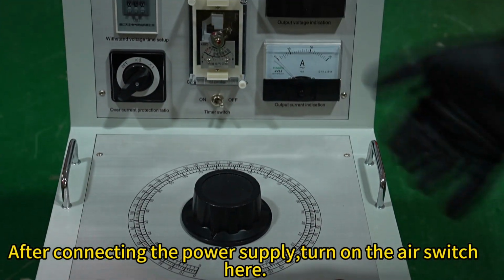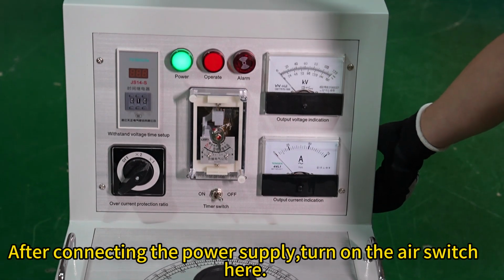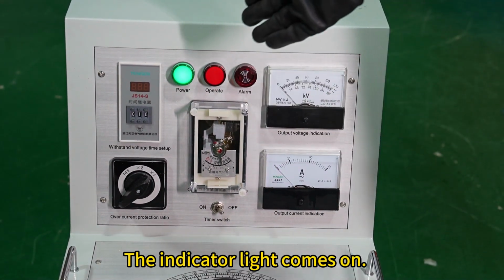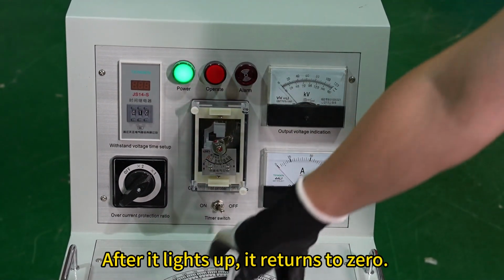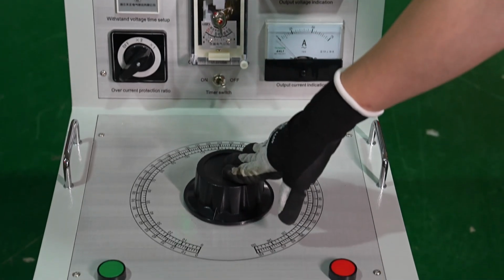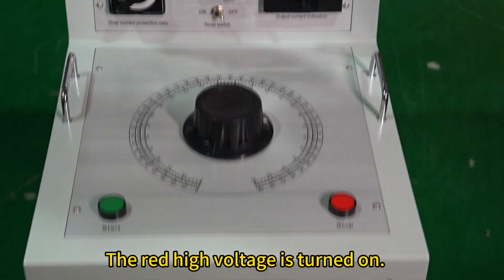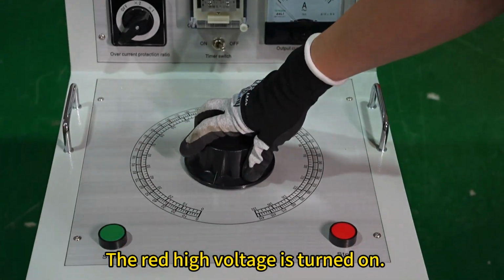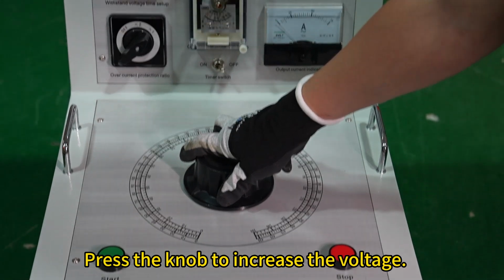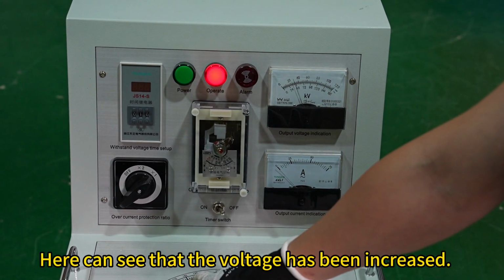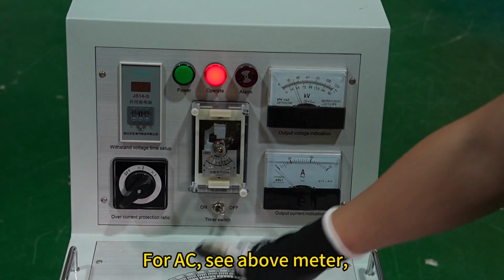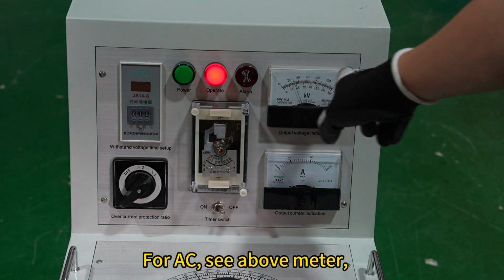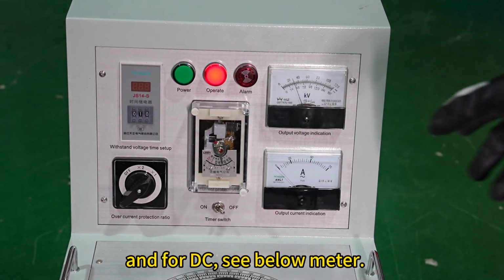After connecting the power supply, turn on the air switch here. The indicator light comes on. After it lights up, it returns to 0. Click Start. The red high voltage is turned on. Press the knob to increase the voltage. Here you can see that the voltage has been increased. For AC, see the upper meter, and for DC, see the lower meter.